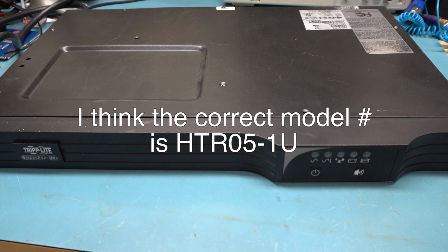This particular one is a line interactive UPS, which means it has an auto transformer with a bunch of relays and taps which will adjust for the incoming line voltage. In North America it's 120 volts. If it goes down or up, I believe this goes down to 90 volts and it will still be able to compensate, adjusting the different taps on the relays and transformer to keep the output at 120 volts even if the input varies.